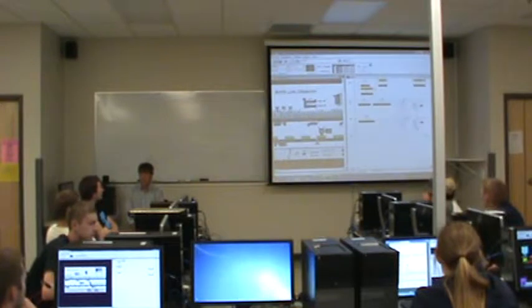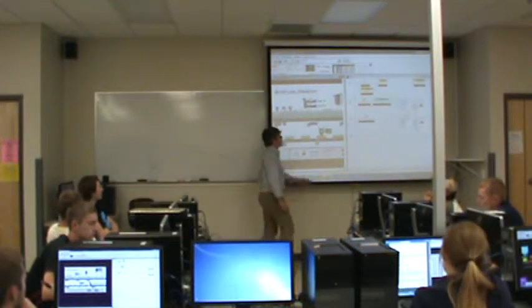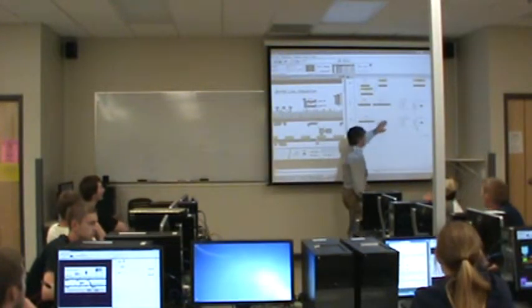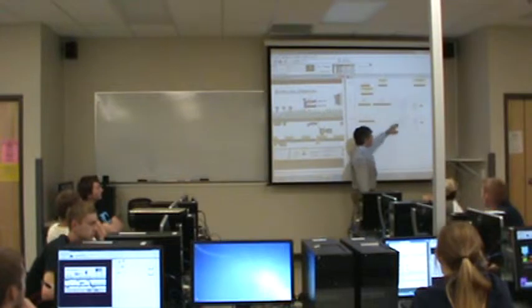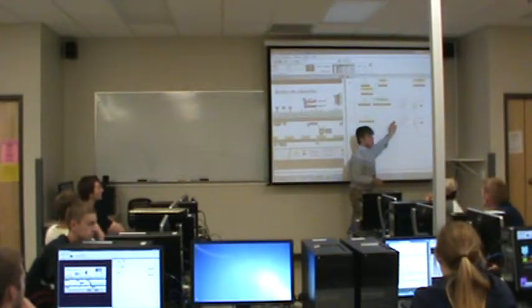You see how counters and timers are really basically the same thing. It's just that a counter will count up based on events that are triggered on the rung preceding the count instruction. And timers just add up time continuously when the rung preceding them is true.